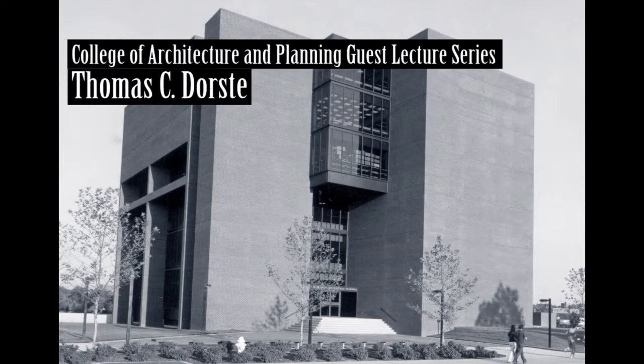And this is where an owner says to me, why in the heck don't you use a 1,000-watt Lucalox, which has 133 lumens per watt, rather than a power groove fluorescent, which only has 69, or a high output that has 75? Okay, I point out to him, it has a 24,000-hour life. The fluorescent has a 20,000-hour life. But at 40% of life, that one is down to 118 lumens per watt, and the power groove is still 63. At the end of the life, the power groove at the end of 20,000 hours is 59, the Lucalox is down to 53. So it'll last forever. It'll last 24,000 hours, but at about 12,000, you're getting half the light out of it you started with. So you have to watch for that kind of a bug in the engineering data that's published on light fixtures. I'll quit.